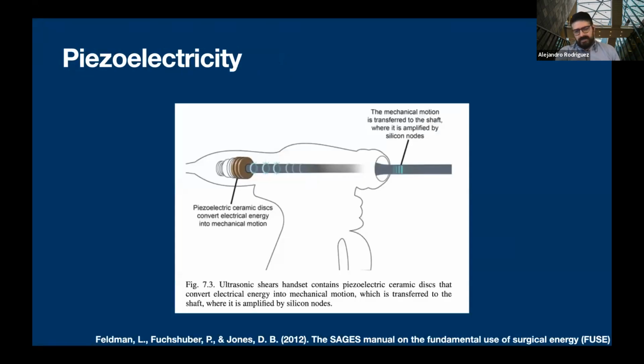This ancient discovery actually translates into the device we use today, the ultrasonic device, because it uses piezoelectricity to energize ceramic discs. These ceramic discs are not on the device itself - they are placed on the cord, which we call the handpiece in Spanish. So these discs are actually in the handpiece and not on the disposable single-use device.